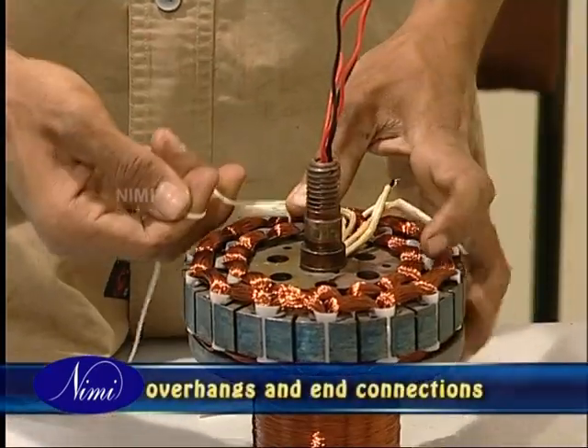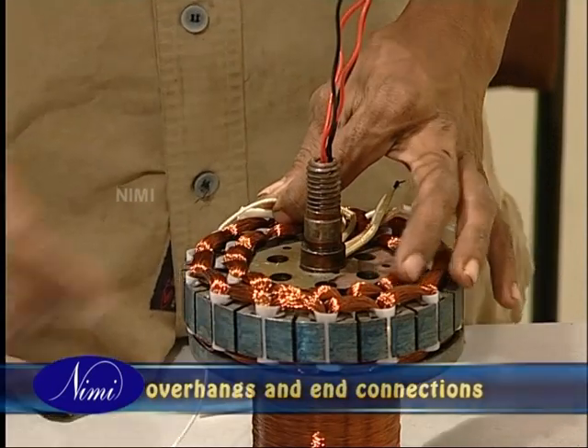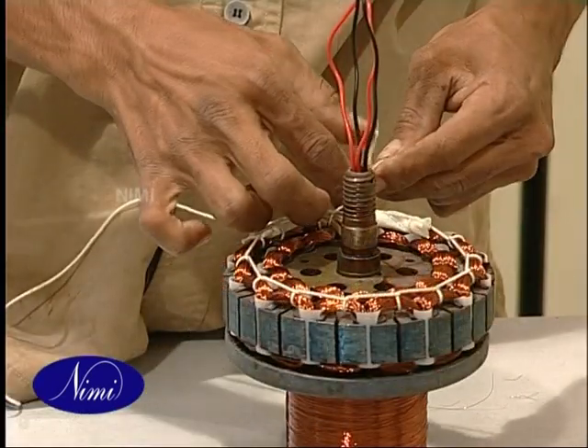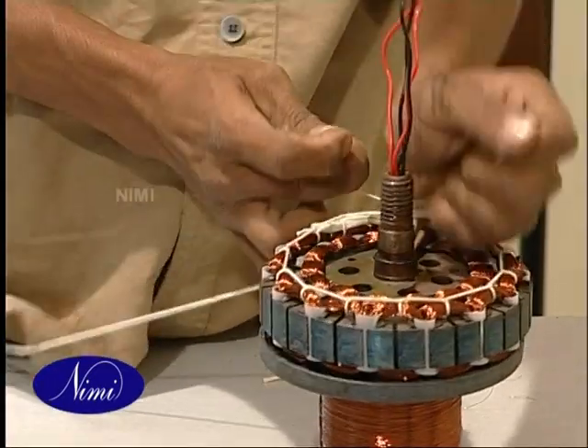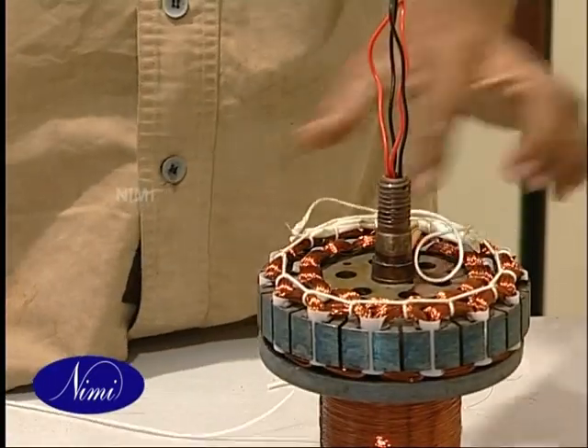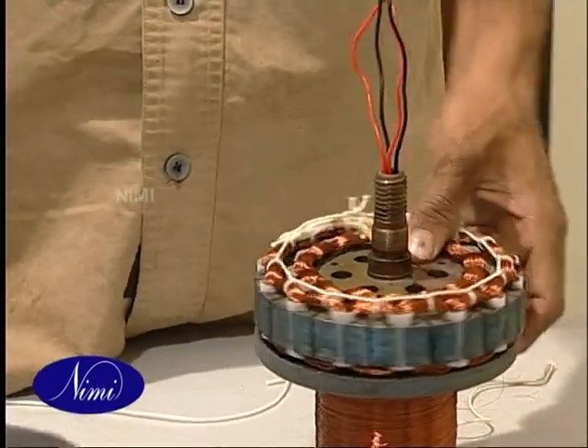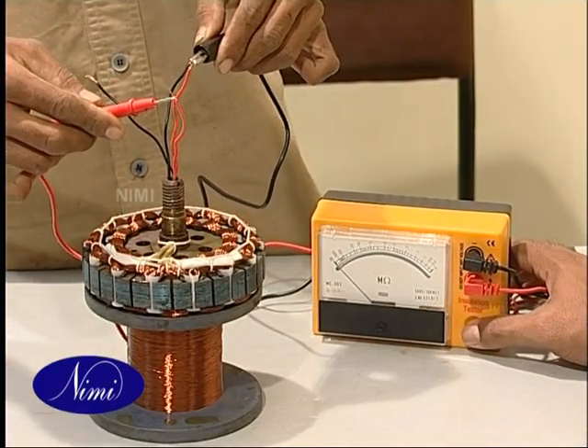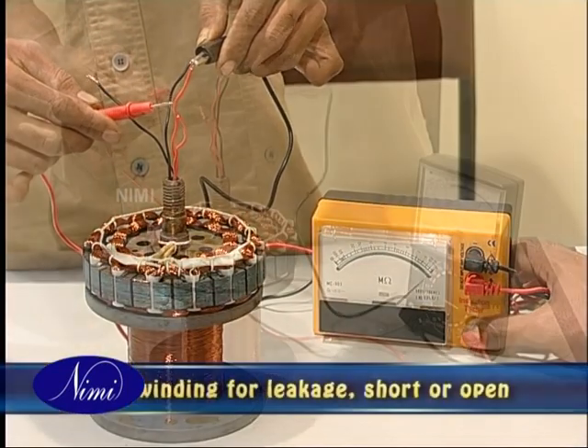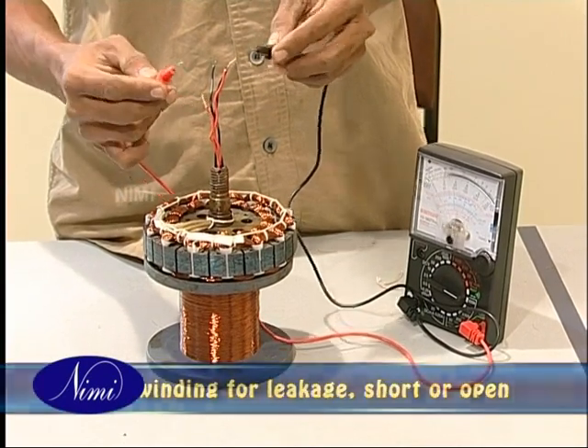Bind the overhang and end connections with the help of a binding thread or a tape. Take care to check the dimensions of the overhang such that it is the same as in the original winding, so that the winding does not rub with the rotor. Using a megger and a multimeter, test the winding for insulation leakage, short or open circuit.